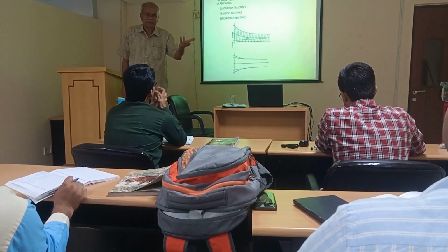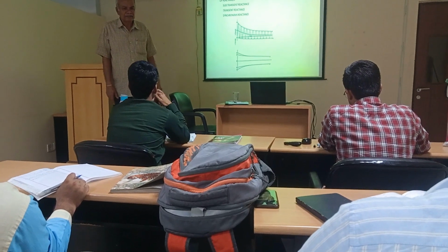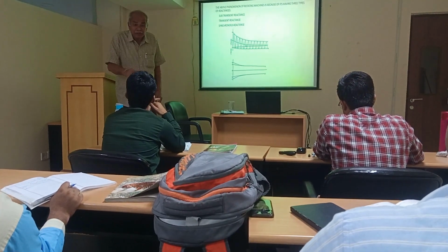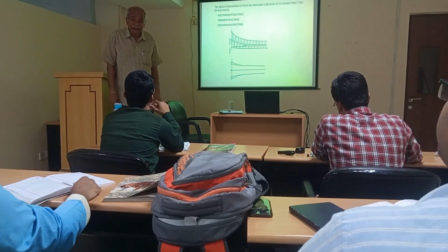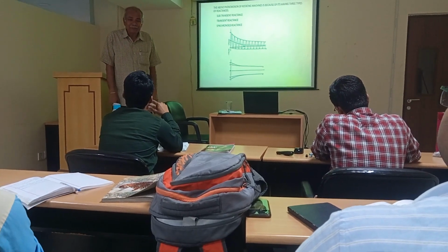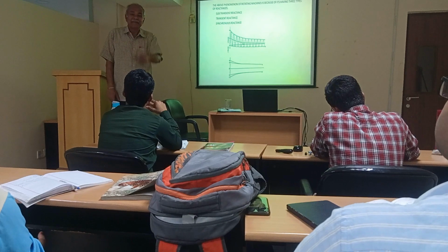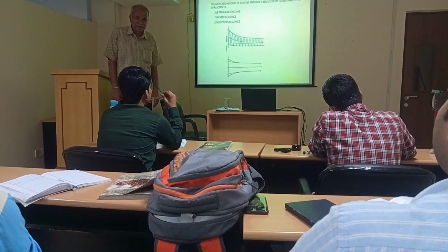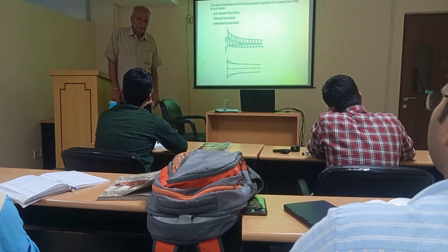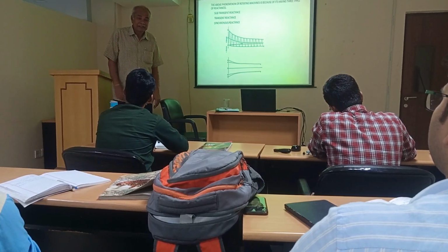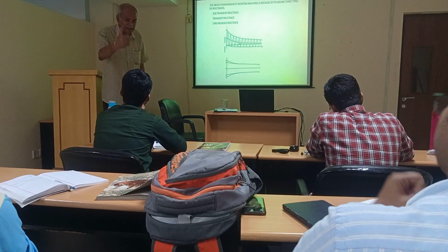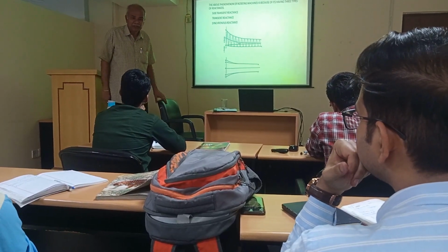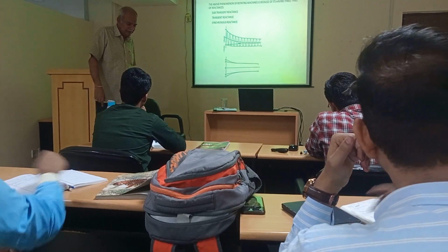Synchronous reactance is the steady state. It is a peak to peak value, so I divide by 2, then we have to divide again by √2 to get an RMS value. For calculating reactance, we have to convert voltage to RMS. This is the practical method of calculation of transient reactance and subtransient reactance.